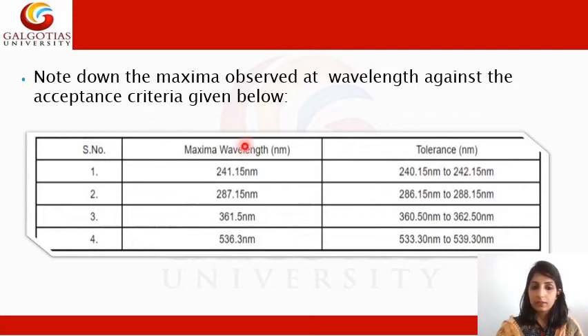These are certain wavelengths that should be obtained whenever you are performing a scan. First is 241.15 nanometer, and there is a tolerance range within which the value should lie. Second 287.15 nanometer, third 361.5 nanometer, and then 536.3 nanometer. These are the wavelengths where the maxima should be obtained. The absorbance should be high at these wavelengths, within the tolerance range. Whatever values we are taking, whatever method we are using for the calibration, we obey the IP. According to the IP, the instrument is calibrated. Whatever method is written in the pharmacopoeias, the IP, the British Pharmacopoeia, the USP, we follow the same procedure for the calibration.